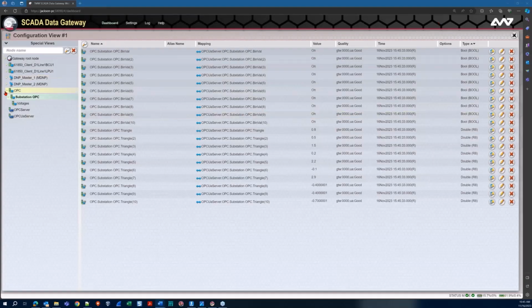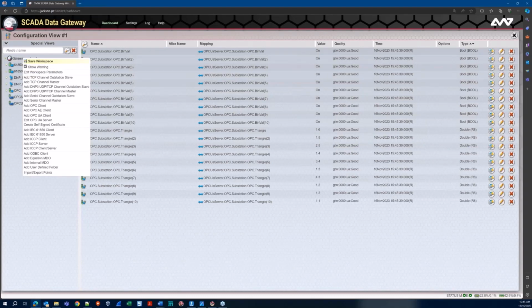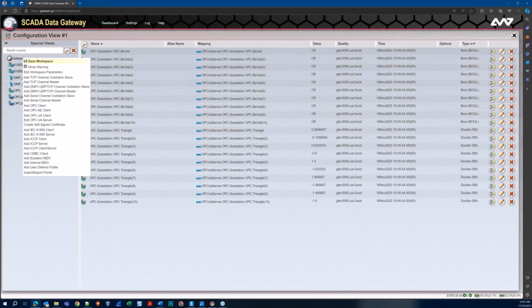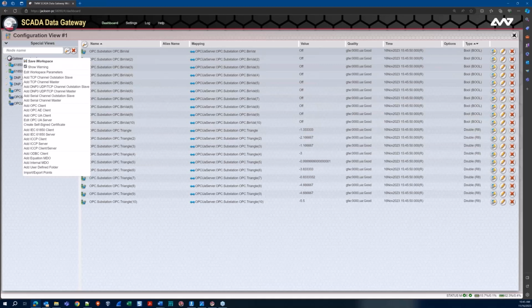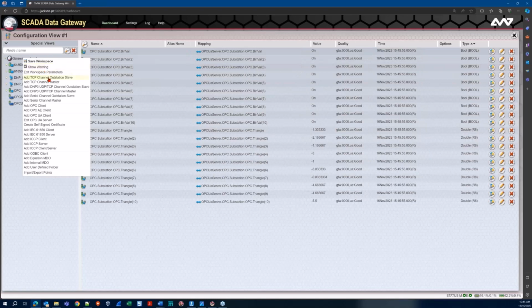Just like I did for OPC, DNP3, and 61850, in order to create that 104, I need to create what I believe is called a 104 controlled station, though you could call it an outstation or slave depending on the protocol. The terminology changes, server for 61850. So to do that, I'll come back in here, and just like I created my DNP master by clicking Add TCP Channel Master, in this case I'll click Add TCP Outstation Slave.